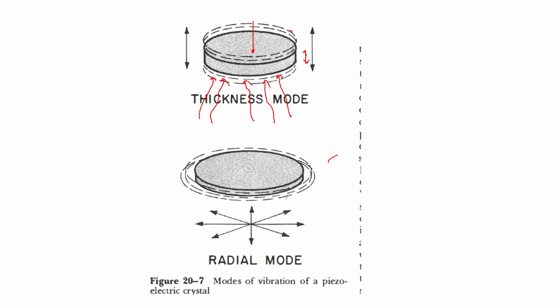And when it vibrates, first it changes its shape. This vibration can be seen either in thickness mode, where it vibrates like this, or it can also vibrate radially. So there are two modes of vibration of this piezoelectric crystal. One is the thickness mode, where it will vibrate up and down, whereas the other, the radial mode, vibrates in different directions. When it vibrates, this vibration converts the sound energy into electrical energy, and this electrical energy is taken up from the electrodes to the display or computer, where the image is produced.